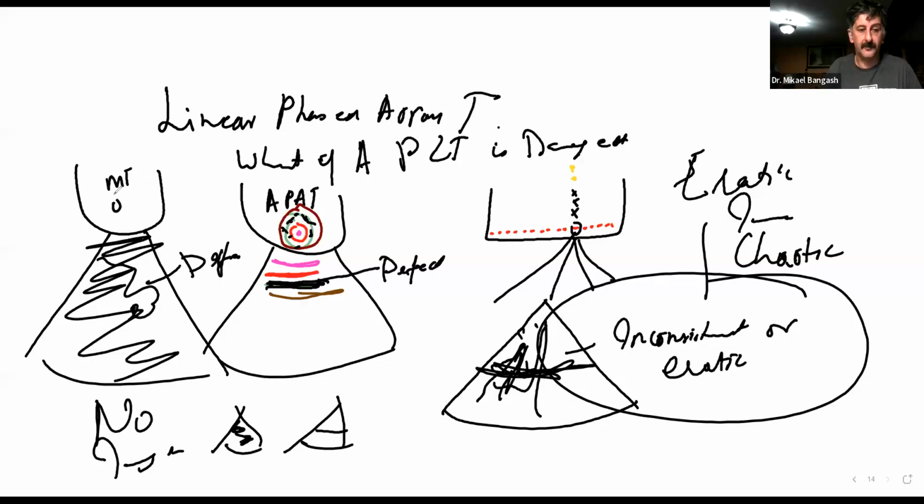What else did you say? Well, in your mechanical transducer, we look at the image and say, this doesn't look good, because we have no image, which means there's something wrong here. Clear? Did that make sense? Yeah, so it won't be no image. Exactly. But that's when I talk about your mechanical.